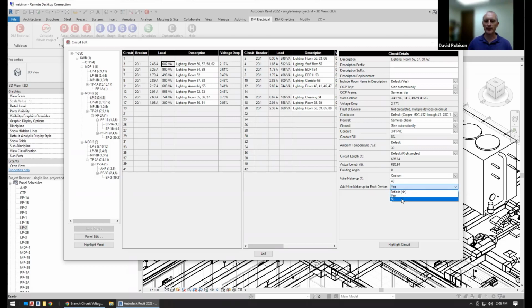If it's not for each device, if it's just once, that's maybe if you've got your panel at a different elevation, so you're going up and then down once. So if you need to add additional length to what we calculate, that's what the wire makeup is for. And you can do it once or per device on the circuit. If you have a fixed length and you've typed it in, and you also specify a wire makeup, we are going to add them together. That's what this actual length ends up being. It's where we show you here's the number you typed in, you also gave us this 40, we assume you want to use both of those numbers. So we're going to use 90 feet as the length of this circuit.